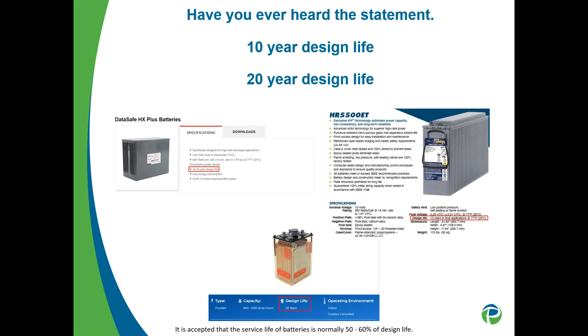Typically what's happened is that 10-year design - actually EnerSys is pushing a 10 to 12-year design - and the service life is typically about 50 to 60% of that. That's based on a couple of things, float voltage being one of them, but there's a number of items involved. So there's a lot of misconceptions of, hey, this is a 20-year design life, but I know I'm only going to get 12 or 15 - that's where the mix-up happens.